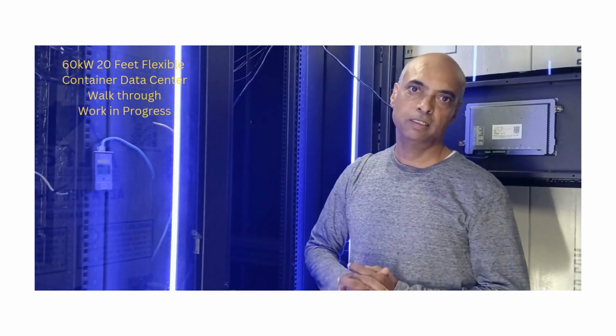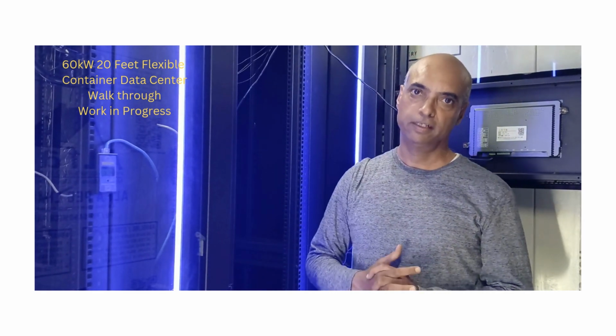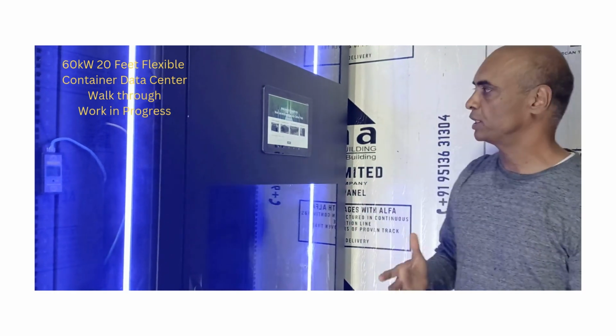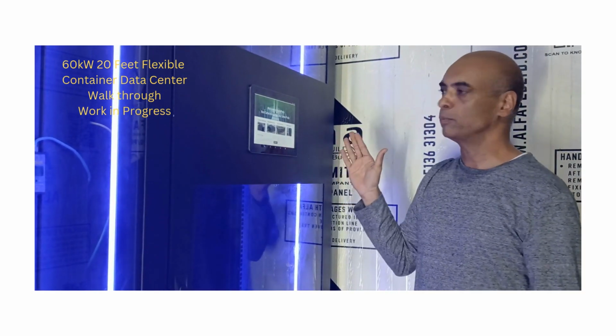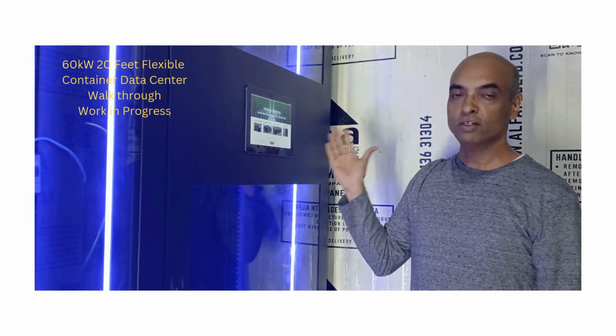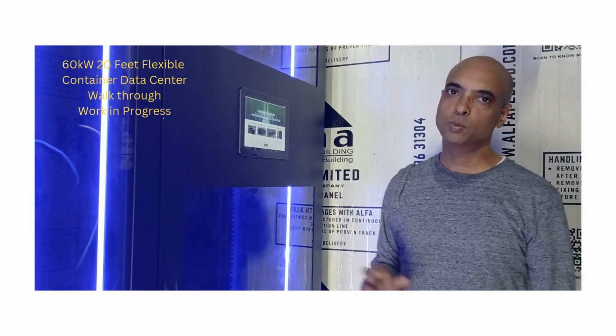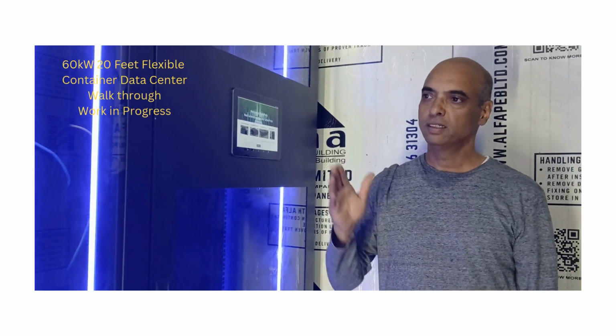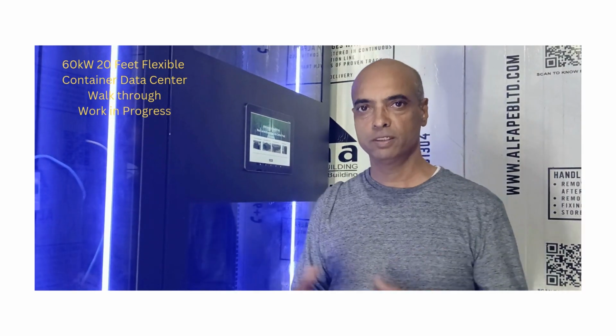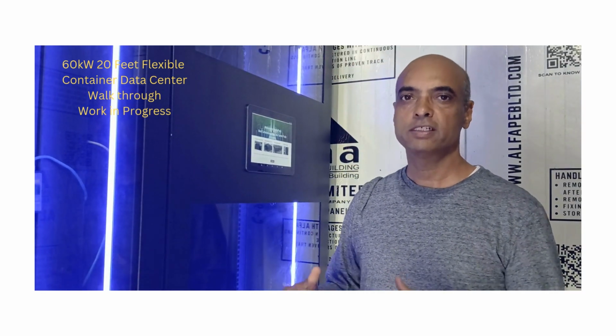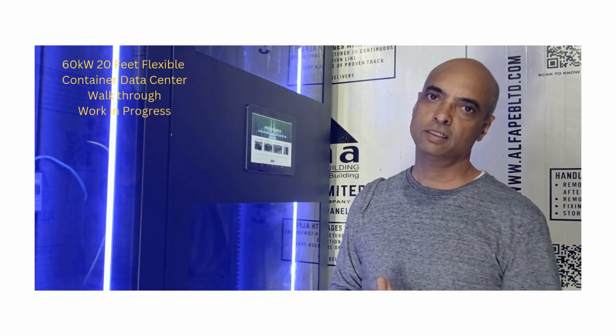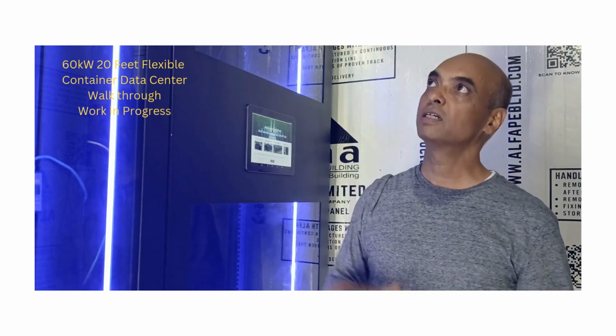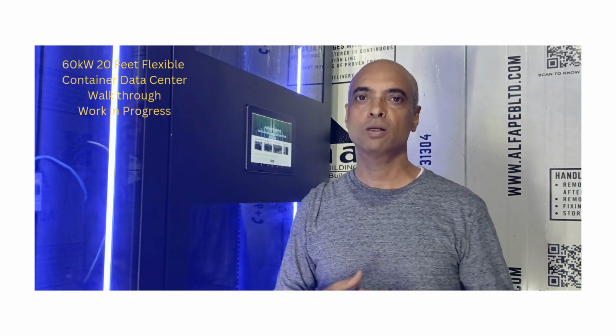This is a very customized IT rack purposely built for the containment zones. The technician can immediately see the temperatures and what's happening in each IT rack through the display, which shows all the temperatures and humidity in each environmental management system. If there's a water leakage, an alarm will trigger, and if there's smoke, an alarm will automatically come out, so technicians know what's happening in each IT rack. Let's test it and see how it works.